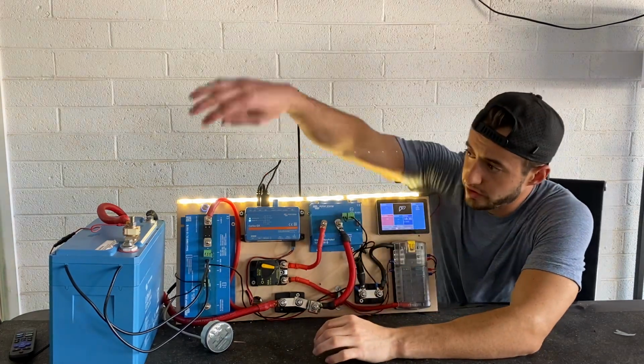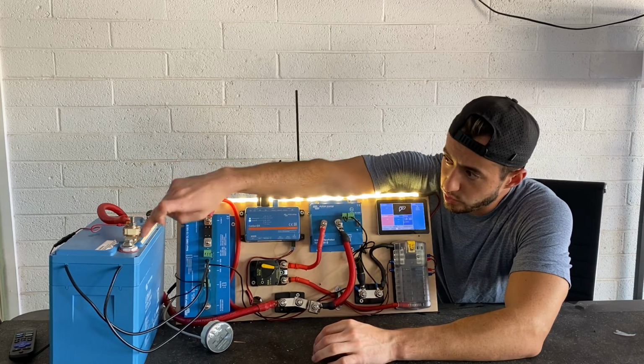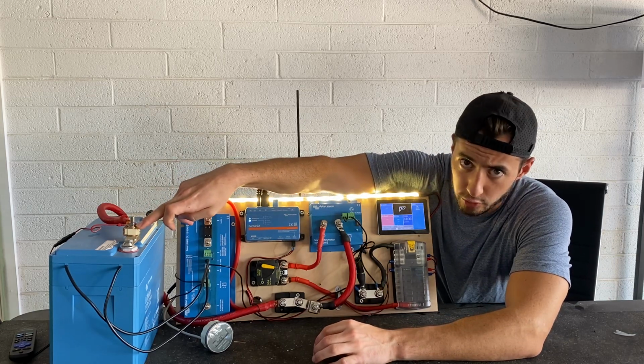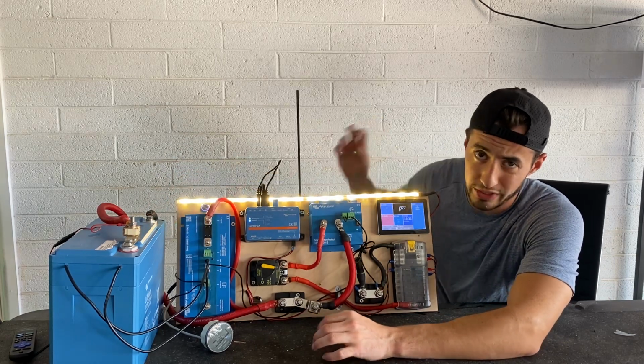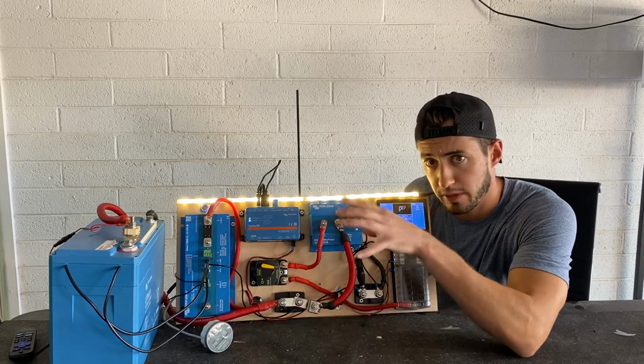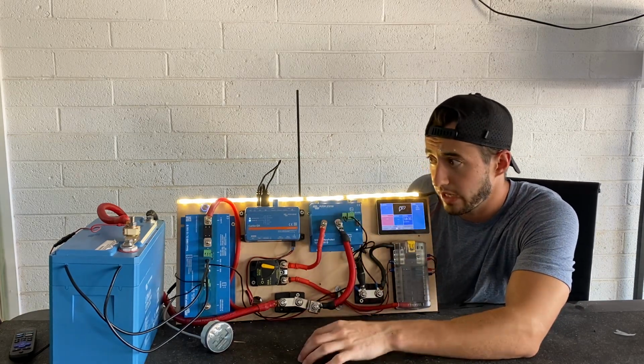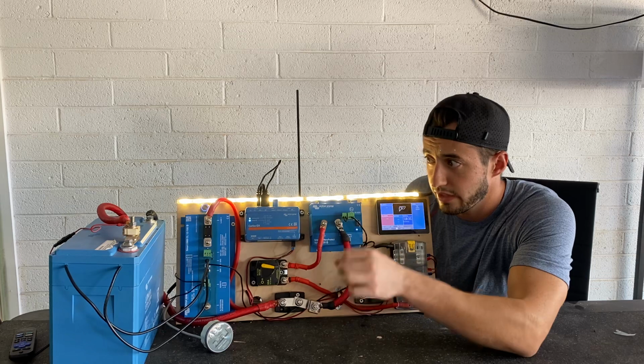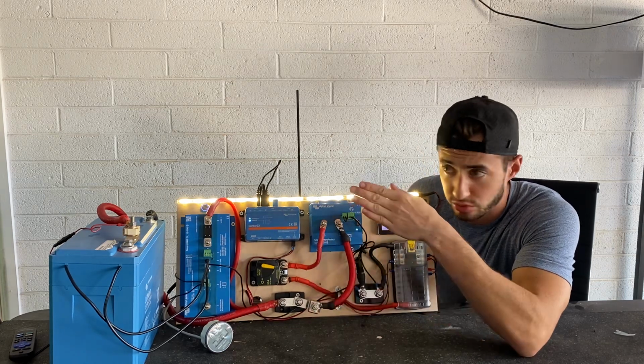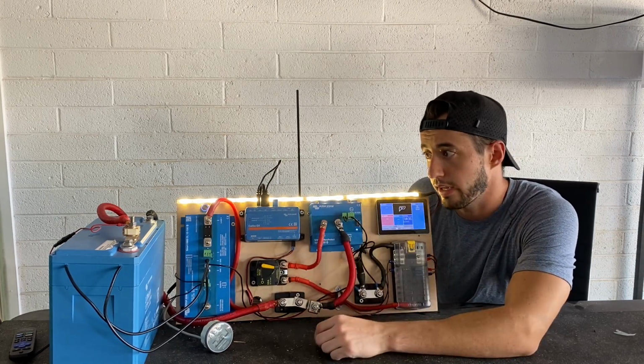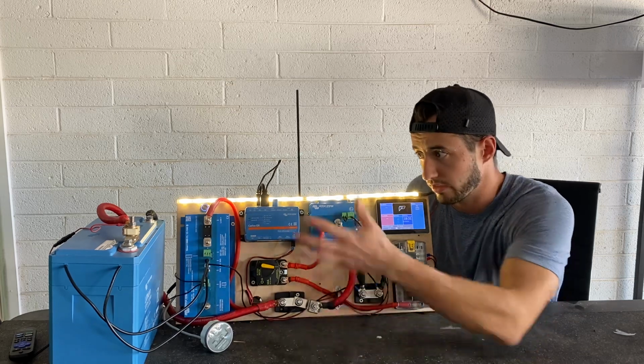So starting over here, we have a 250 amp terminal fuse, which has the appropriate MRBF rating for a lithium battery, so that if there is a short circuit event, this fuse is capable of actually splitting that current and not melting and welding to the battery.